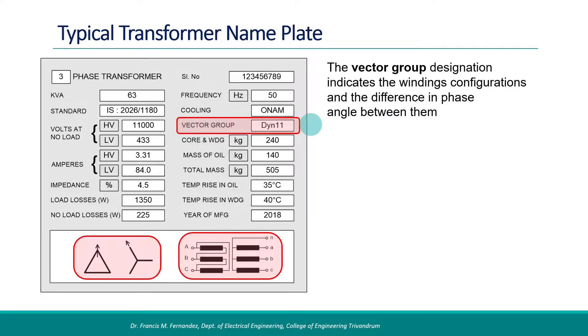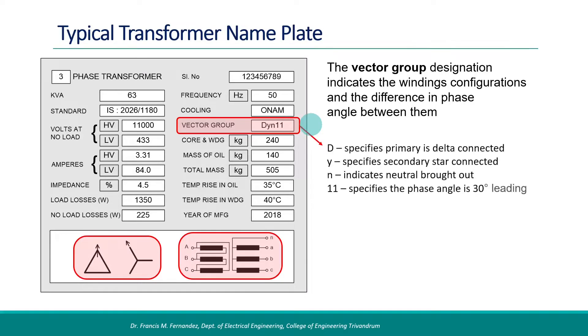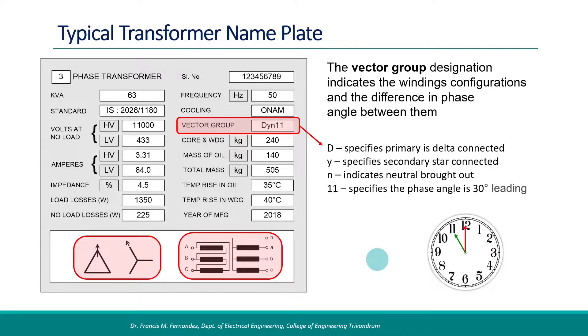What is the meaning of dyn11? The uppercase letter D specifies the primary is delta connected. Then the lowercase letter Y specifies star connection in the secondary. N indicates that the neutral terminal is available. And the number 11 specifies that the phase difference is 30 degrees leading. The number 11 corresponds to the hand position of 11 o'clock on the clock dial, and the angle between the clock hands is 30 degrees. Continue to watch this video to see how the phase shift occurs in three-phase transformers, in commonly available vector groups, and how we can identify it from the nameplate details.